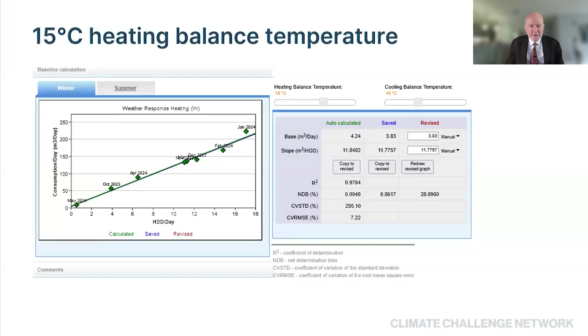Running regressions on Steve's schools — this is a pretty picture everyone understands: monthly gas consumption against heating degree days per day. In the top right corner is the slider that optimizes the heating balance temperature at 15 degrees. I expected the number to be lower, but 15 degrees Celsius is what these schools, all four of them, are running to. That's the adjustment we make for climate zones.